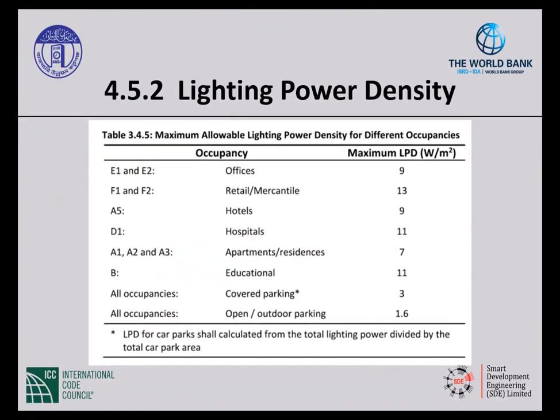All right, lighting power density. How much light wattage can we put in our spaces? This is broken down by the type of space. The type of space will tell us how many watts per square foot we can have for each of those spaces. So it's set in this table. It's provided for the respective functions with all the building occupancies.